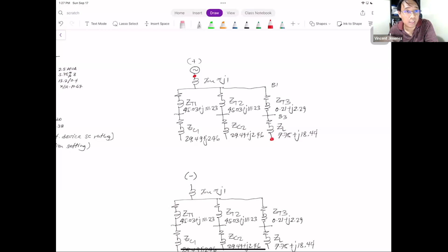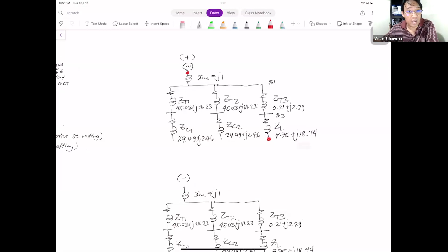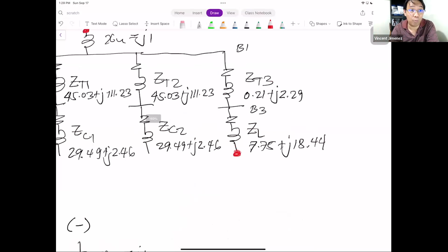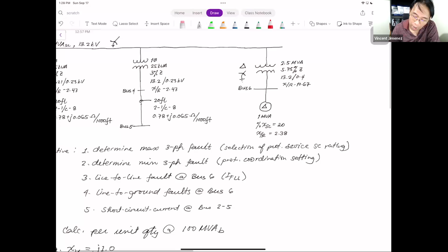When we say maximum fault, the contribution is still present. When it's minimum fault, meaning 30 cycles have elapsed, your ZL loses its contribution because of the decay. The momentum of the rotor is lost, so it no longer generates the voltage that produces the short circuit current. Only the utility remains. So that's for the minimum. We will compute for the maximum first, then for the minimum. Okay, objective number 1.